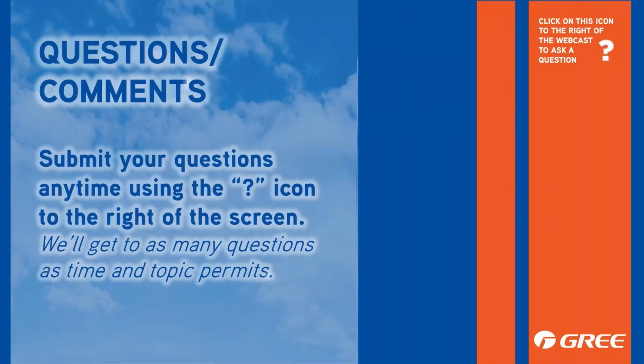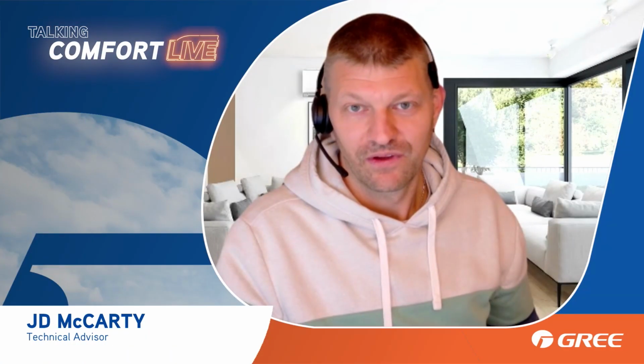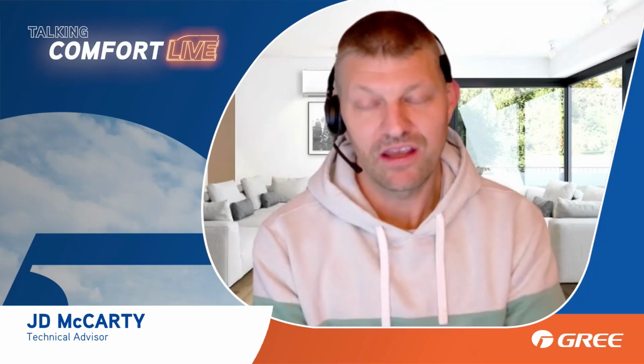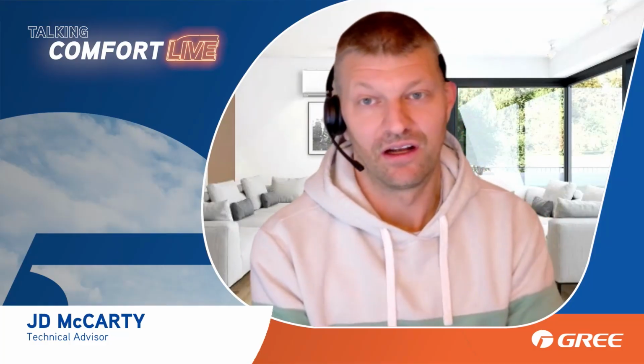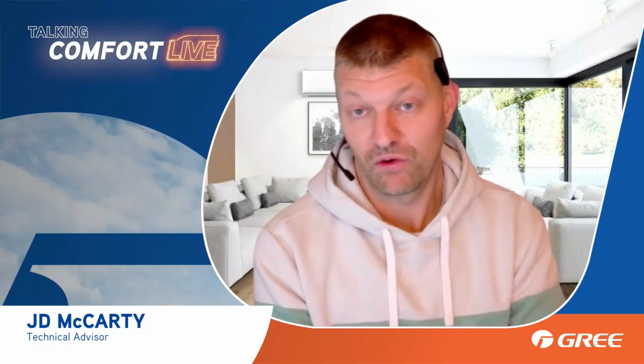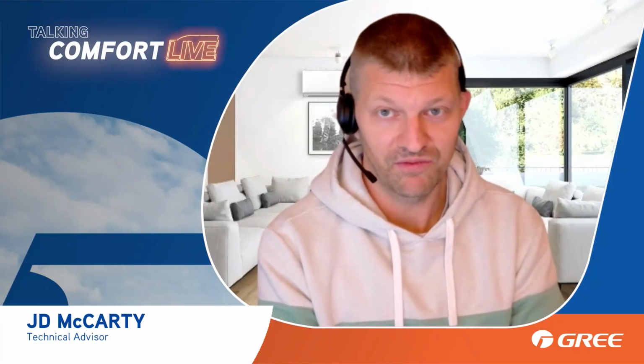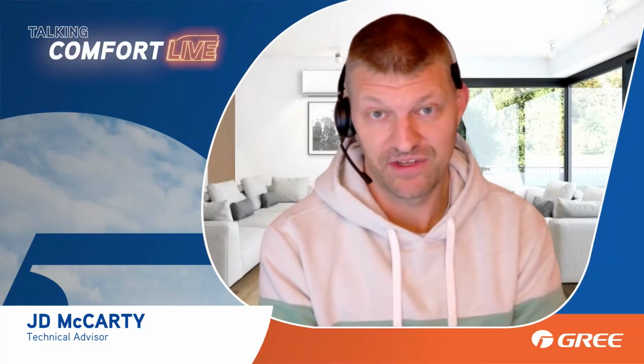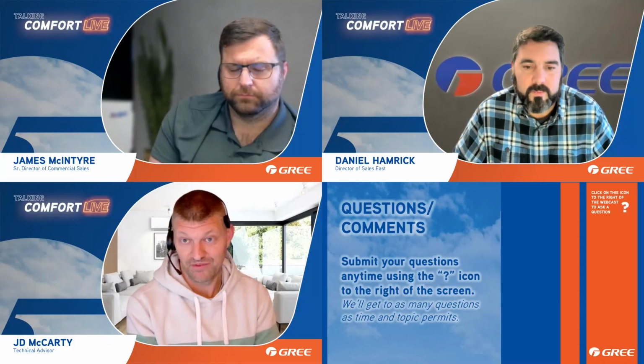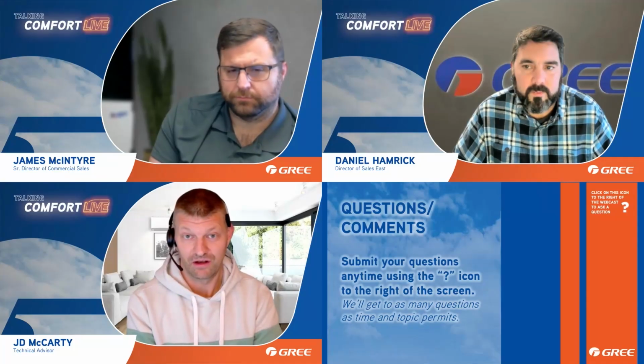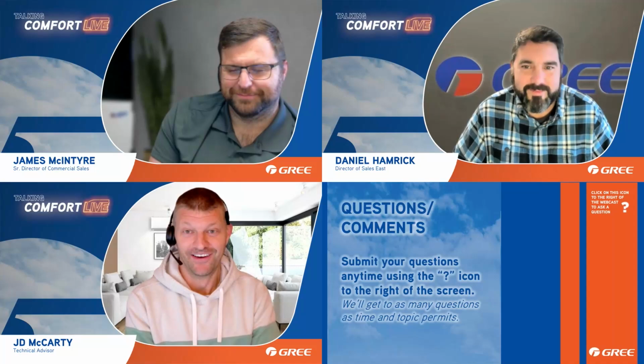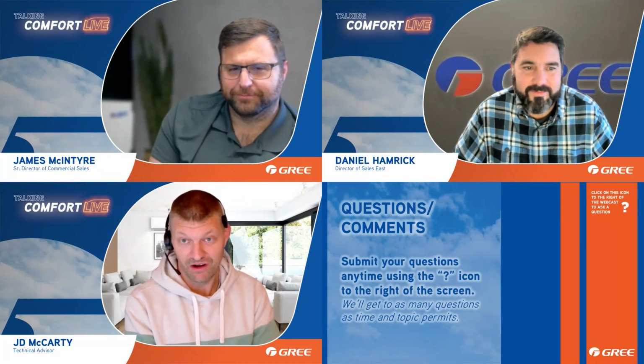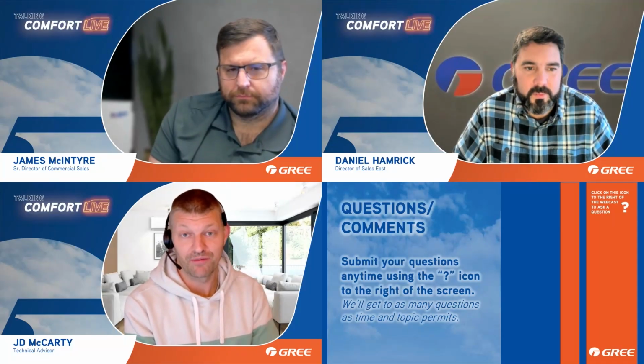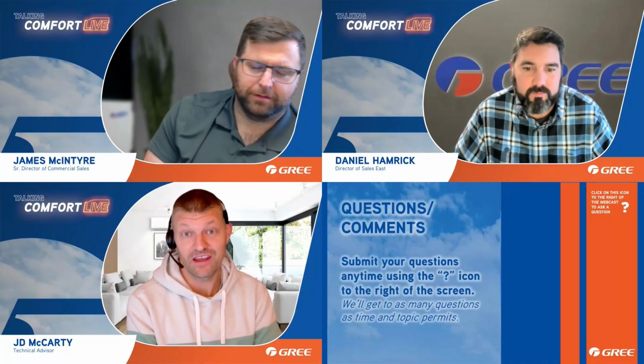All right, next question. How dependable are the GREE's EEVs? They never break. No, go for it, JD. You deal with this on the daily. Yeah, I do take calls on people thinking the EEV is bad on a daily basis. Most of the time it is not. Most of the time it might be a sensor. They also have screens that protect them on each side, depending on the flow of refrigerant. There are strainers in there that protect anything from getting inside of it. So sometimes it might be a strainer blocked up if they didn't braze with nitrogen, or like we were talking about, if they used True Blue or something on the flares, getting caught up in there, or just a sensor being off would be the main cause that I see for those not modulating properly. Most of the time it's not the EEV itself.